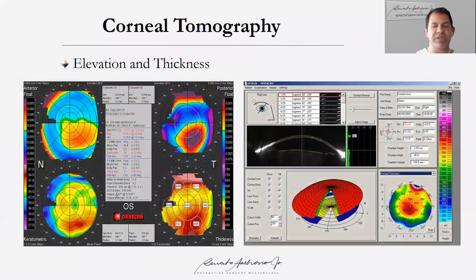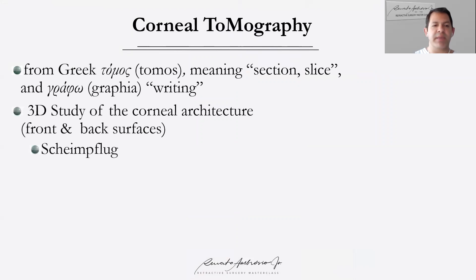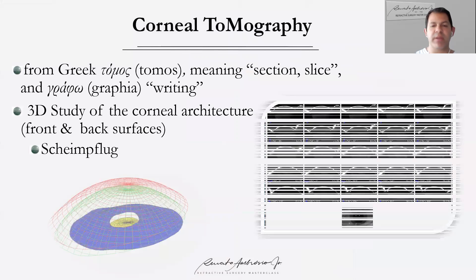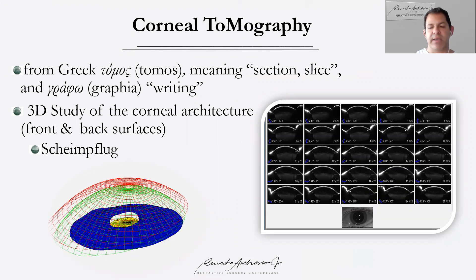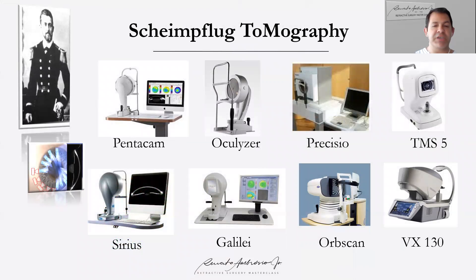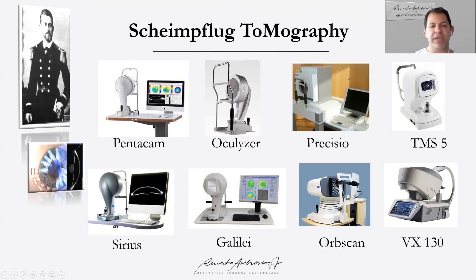When we saw the Scheimpflug images displayed in the Pentacam — also in a rotating fashion — we started connecting this as the future of corneal imaging technologies. Tomography comes from Greek and means to have a cut section of the cornea, and we have a three-dimensional reconstruction from those images connected by the software. We have different instruments from different companies doing rotating Scheimpflug imaging, and also the classic Orbscan with horizontal scanning, and the VX-130 with superior and inferior scanning. Today, the rotating fashion is probably the most common and most advantageous approach.